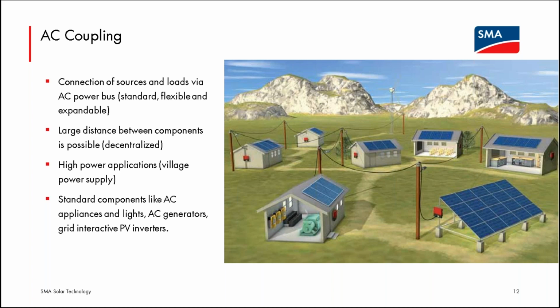If you wanted to double the number of houses in the scenario, and there was more power than those 3 Sunny Islands could handle, what you need to do is just make sure that the loads panel and all of the PV systems that are added are consolidated on a separate AC loads panel that a separate cluster of Sunny Islands would manage. Both groups of Sunny Islands can access power from the same generator or the same grid, but they will have a separate battery bank and they will power separate loads panels.